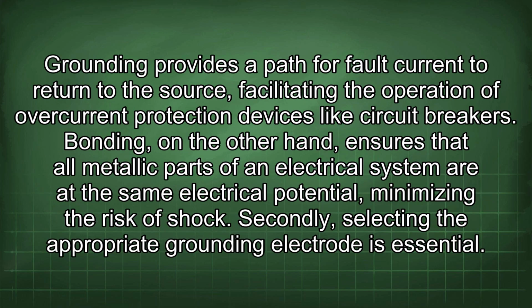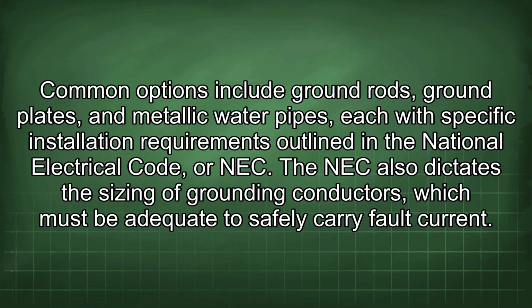Grounding provides a path for fault current to return to the source, facilitating the operation of overcurrent protection devices like circuit breakers. Bonding, on the other hand, ensures that all metallic parts of an electrical system are at the same electrical potential, minimizing the risk of shock. Secondly, selecting the appropriate grounding electrode is essential. Common options include ground rods, ground plates, and metallic water pipes, each with specific installation requirements outlined in the National Electrical Code, or NEC.